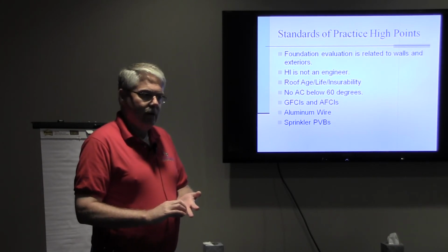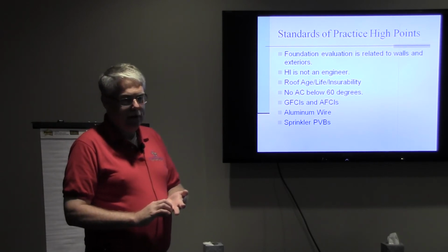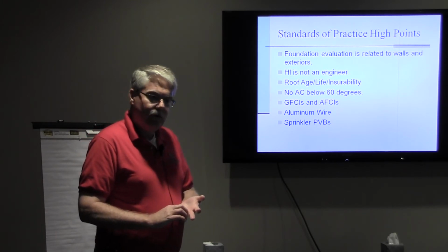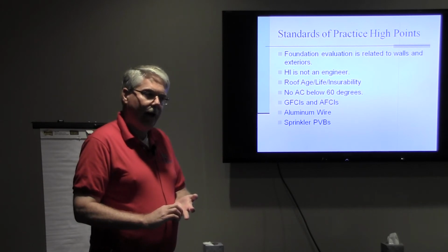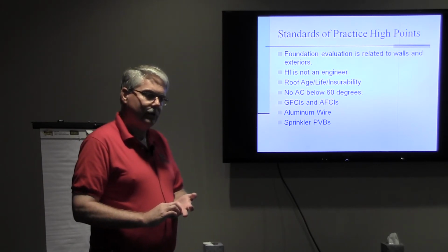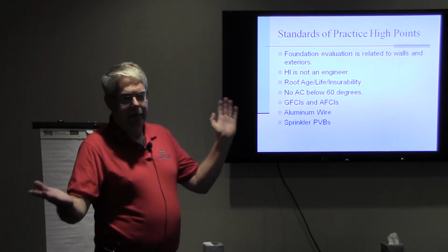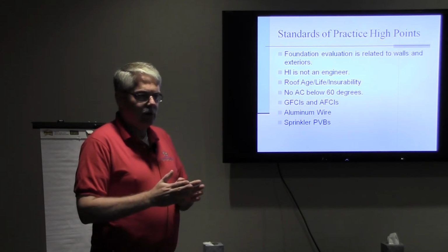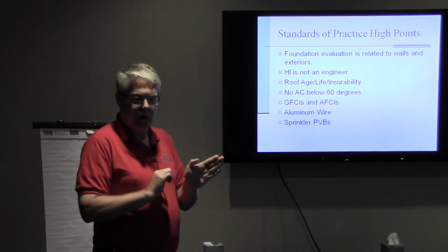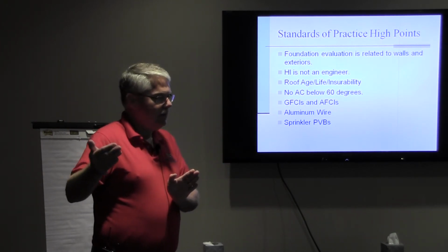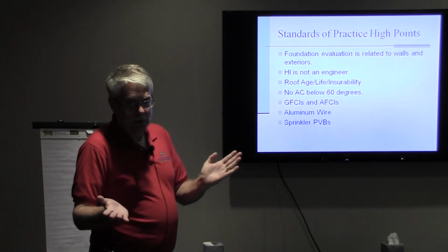Now, in 2004, new construction homes had to have arc faults in all bedroom circuits. After 2008, arc faults, once again in new construction, have to be in all outlet circuits in the house that aren't GFI. So now living room, dining room, study, bedroom, everything. Every outlet circuit either has an arc fault in the electric panel because it's a general use circuit in a dry space, or has GFIs located downstream because it's in a wet space, exterior, garage, bath, kitchen. So now every outlet circuit is protected.